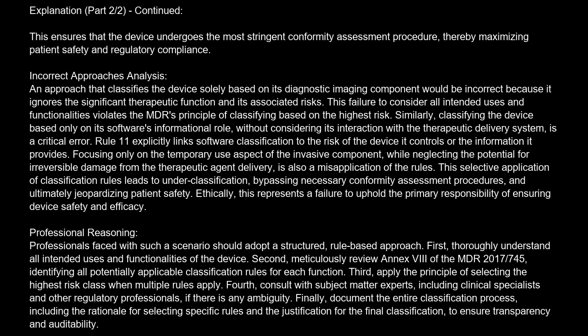Professional reasoning. Professionals faced with such a scenario should adopt a structured, rule-based approach. First, thoroughly understand all intended uses and functionalities of the device. Second, meticulously review Annex VIII of the MDR 2017/745, identifying all potentially applicable classification rules for each function. Third, apply the principle of selecting the highest risk class when multiple rules apply. Fourth, consult with subject matter experts, including clinical specialists and other regulatory professionals, if there is any ambiguity. Finally, document the entire classification process, including the rationale for selecting specific rules and the justification for the final classification, to ensure transparency and auditability.